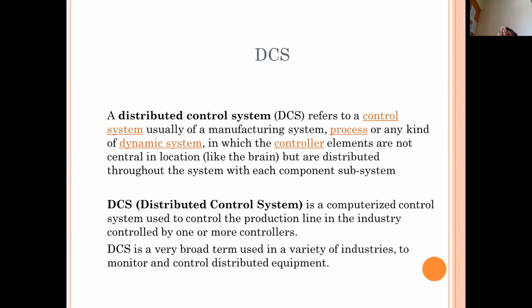It's not that the PLC cannot be used for analog ones. It can be used for analog ones, but for digital, discrete things the PLC is a better controller. And coming to the DCS, suppose you have a tank or a boiler and you want to maintain the level. The boiler's diameter will be huge. If you use a PLC there, for 5 to 10 milliseconds there won't be any change in the level, not even minimal. There is no need to scan the tank every 5 to 10 milliseconds.